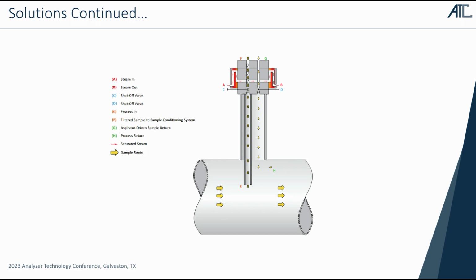Looking back at the top of the probe again, we have steam making its way from the left-hand side out to the right-hand side to ensure that we have adequately heated our sample. So to recap, such a design addresses the hazards associated with hydrogen sulfide by utilizing a simple and compartmentalized design. It handles the corrosive nature of the gases involved by being specifically designed for that. And it's equipped to prevent the formation of solids or salts that could otherwise foul the equipment.